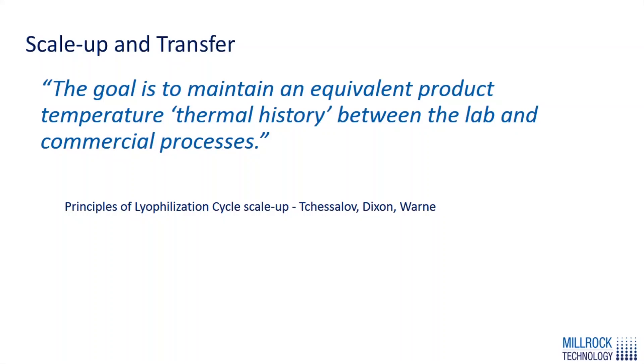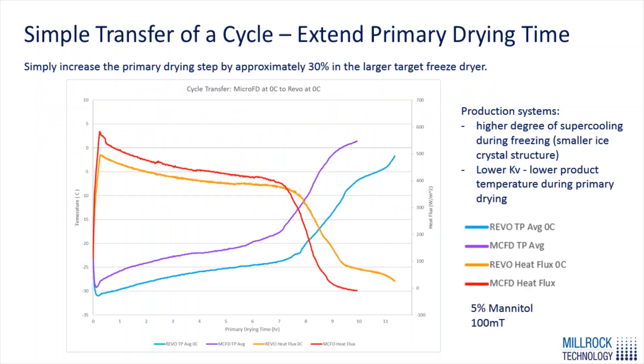Now that we've developed an optimized cycle, we want to look at how to transfer it to a next-size unit — going from lab to pilot or pilot to production. The goal when transferring is to maintain an equivalent product temperature thermal history between lab and commercial processes. One standard safe way to transfer a cycle is to maintain the same settings used on the smaller scale unit and extend primary drying time. The larger the unit you move to, the inherent Kv goes down, so if the cycle runs safely on a smaller unit, running those same settings on a larger unit will be very safe.